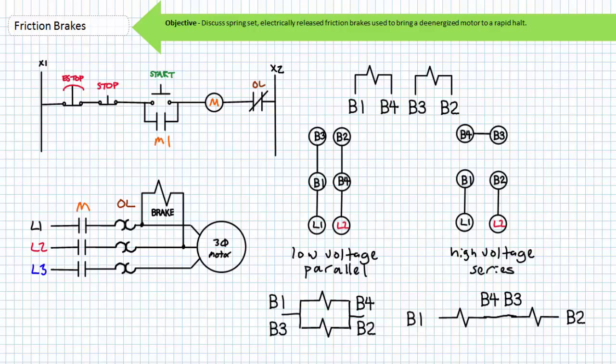Note that fail-safe spring-set electrically-released brakes are applied instantly during power loss, as well as single-phasing events, in which one of the two phases energizing the braking solenoids are lost. Single-phasing and locked rotor conditions by themselves beget large current. Imagine both events occurring simultaneously. It is for this reason overloads are incorporated with motor starters to protect the motor from sustained overloads.